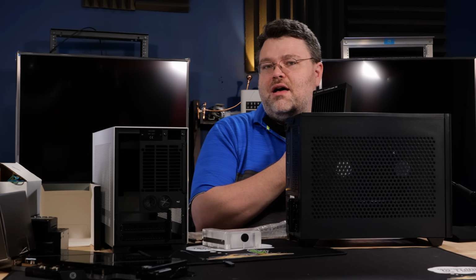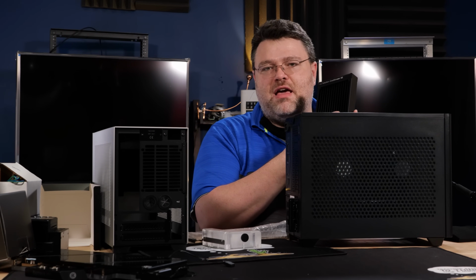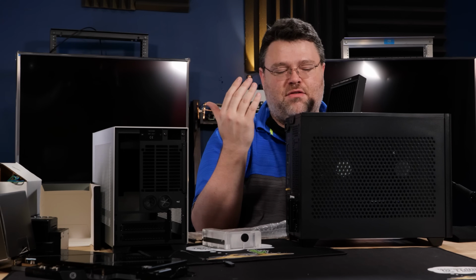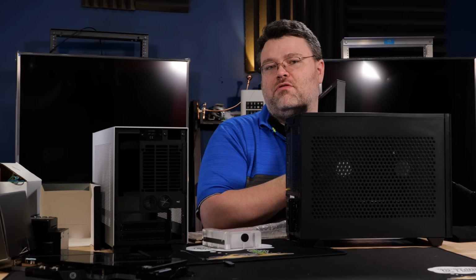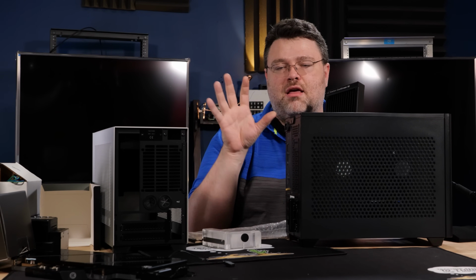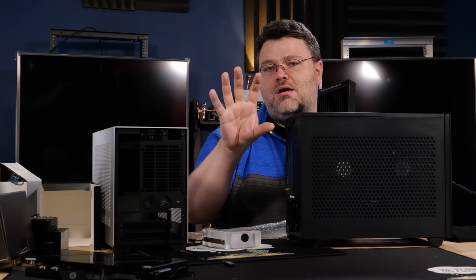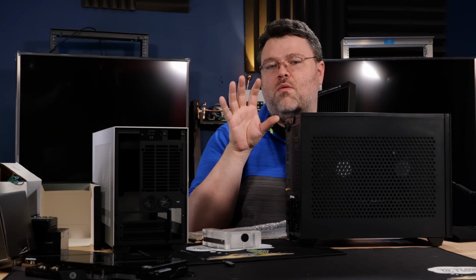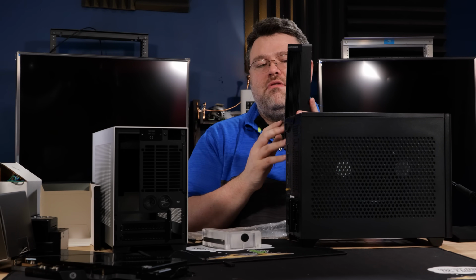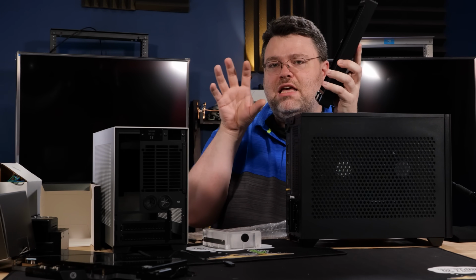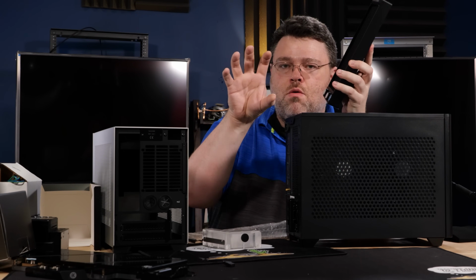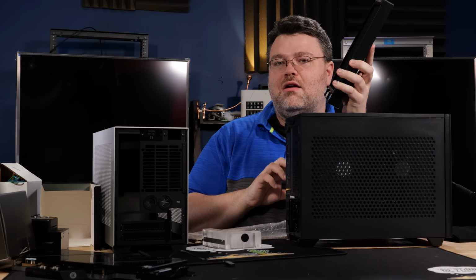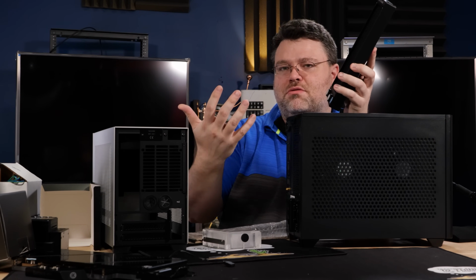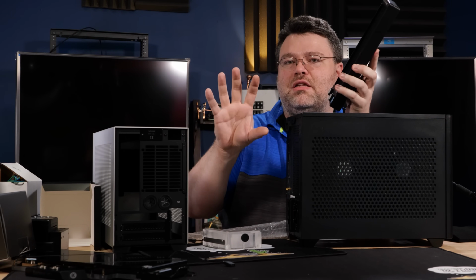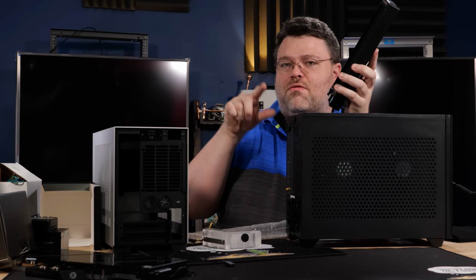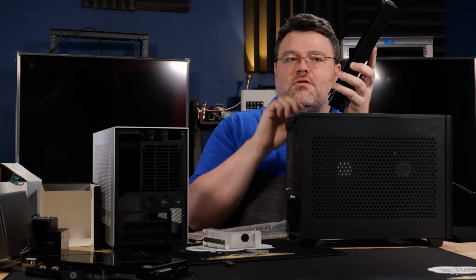What you might not realize is that if you mount the fan so it faces into the radiator, with the back of the fan on the outside, the fan can actually move on its hub depending on the brand. If you have a cheaper fan, as it ages, the fan part will move forward when energized and when working hard, blowing air out the back. It'll actually move on its hub, rub, wear, and slowly lurch forward.